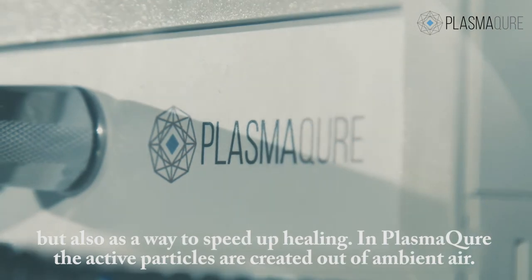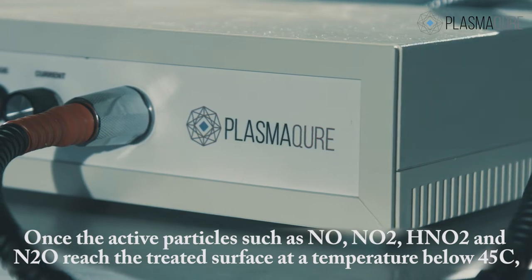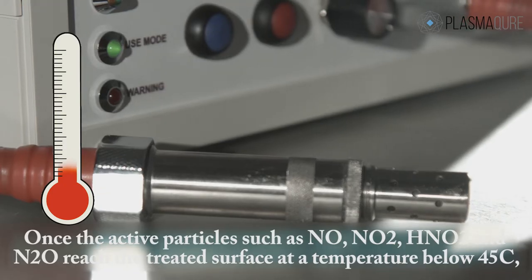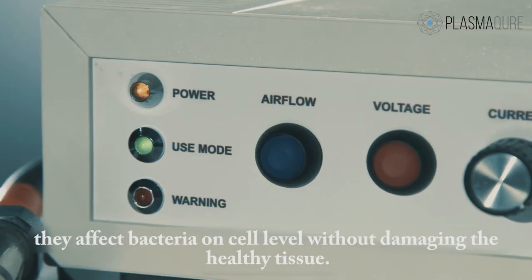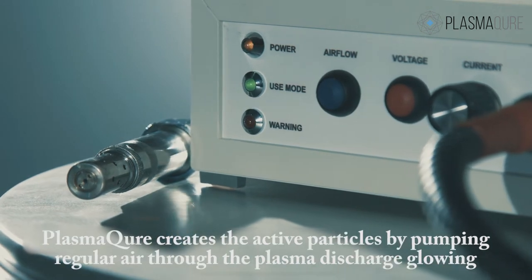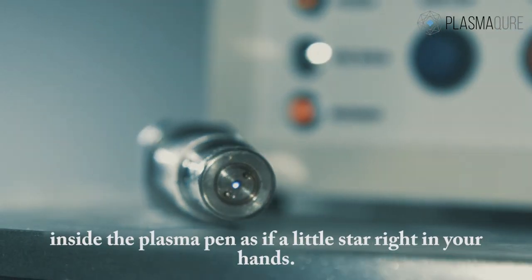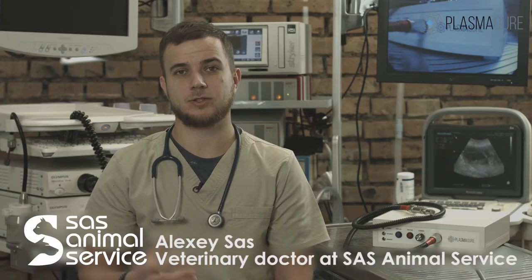In PlasmaQure, the active particles are created out of ambient air. Once the active particles — such as NO, NO2, HNO2 and N2O — reach the treated surface at a temperature below 45 degrees Celsius, they affect bacteria on a cell level without damaging the healthy tissue. PlasmaQure creates these active particles by pumping regular air through the plasma discharge, glowing inside the plasma pen like a little star right in your hands.